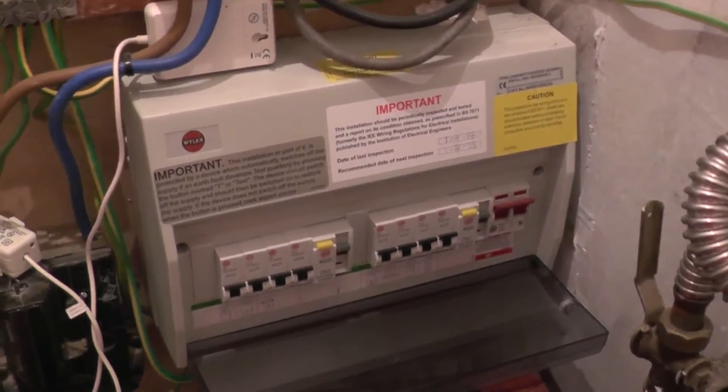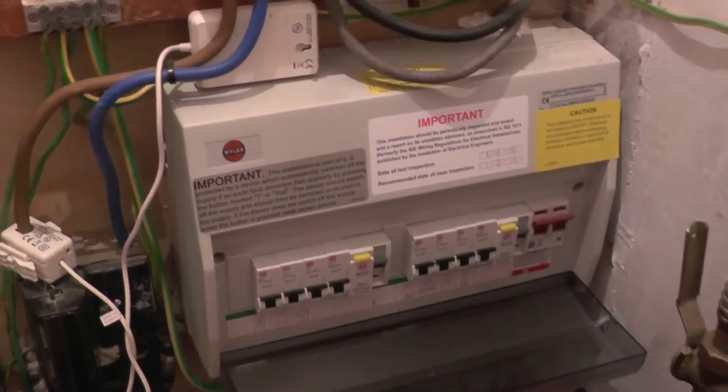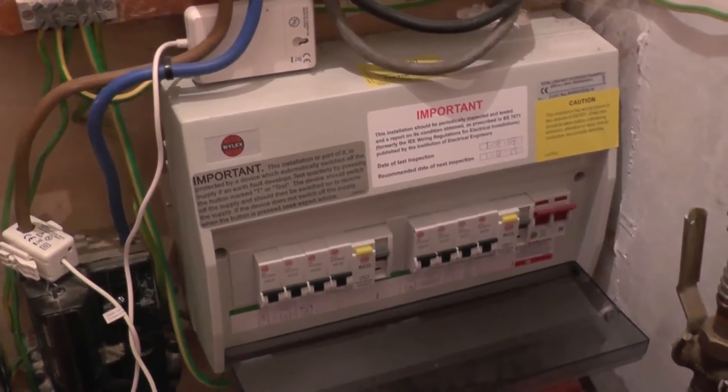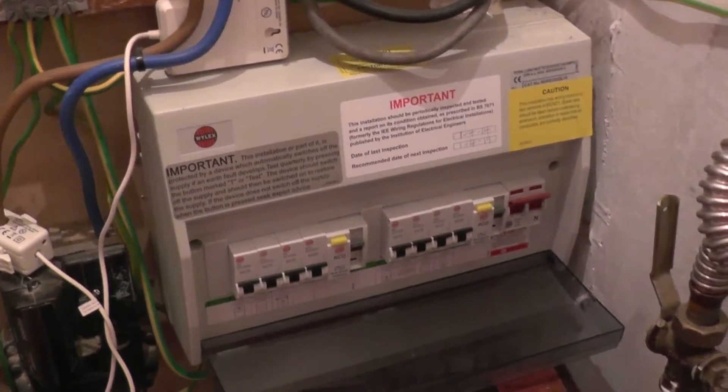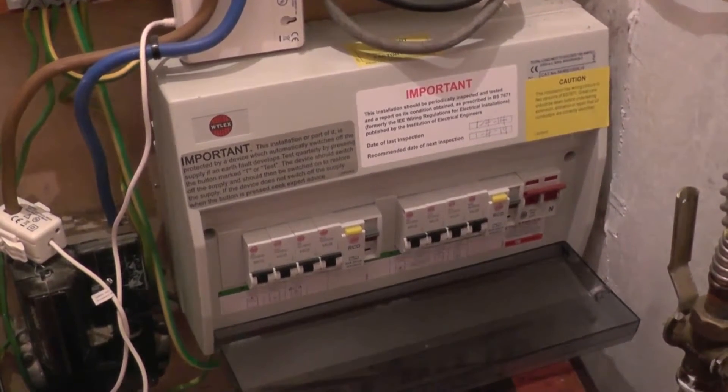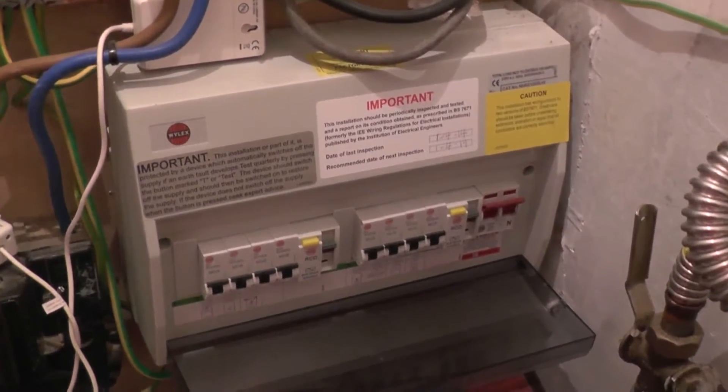But basically he's removed the cables from the fuse board and I'm assuming he's put them into another box. I don't know where he's got his batteries, but if you had them under the stairs I could see problems unless they're sealed with the gases venting. And they're quite corrosive as well.